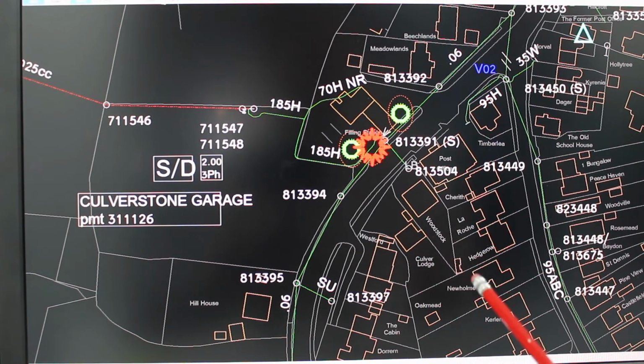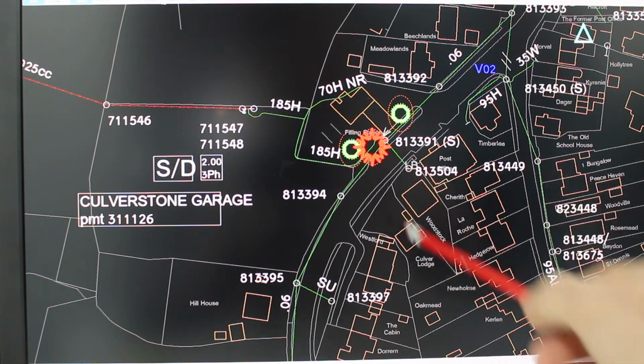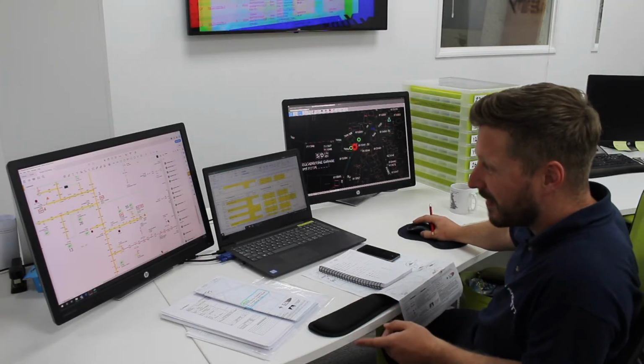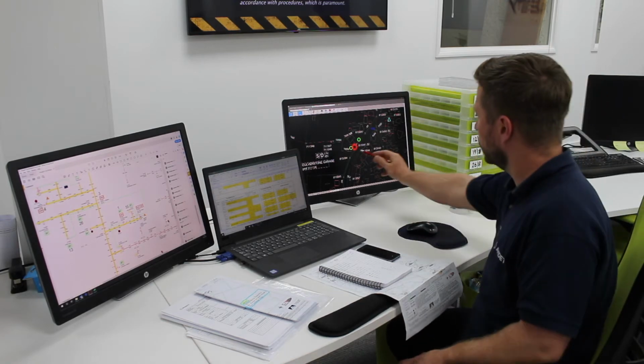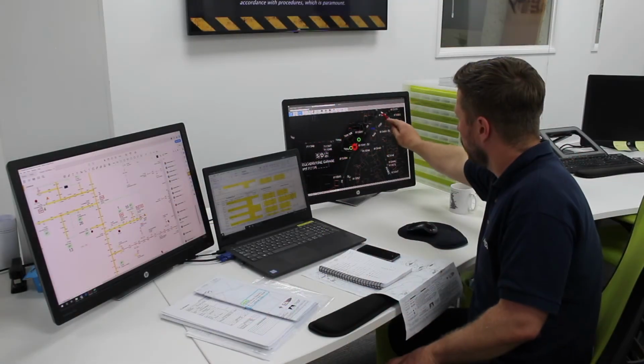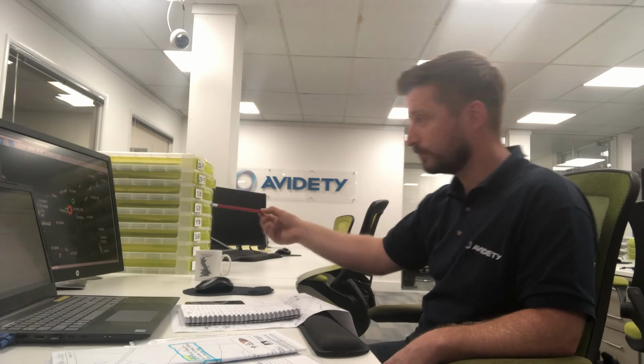Then it comes to another awkward part, particularly challenging. At Culverstone Garage, if you take a look on the power on, there's an open circuit fault out of the underground cable on Culverstone Garage. Now, Culverstone Garage is actually entirely back feedable. Unfortunately, due to the position of the open circuit fault, it means 19 of the 20 customers are fed off the overhead line. They're on backfeed now, unaffected, and the petrol station is being fed from the pole transformer. Now this wouldn't normally be a problem, but if we connect a generator to the pole transformer here, this is actually a decayed pole, so this requires replacement. And as you can imagine, the garage aren't keen to go off what would be a full day's outage to replace a transformer H pole.